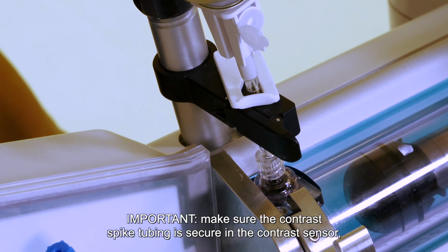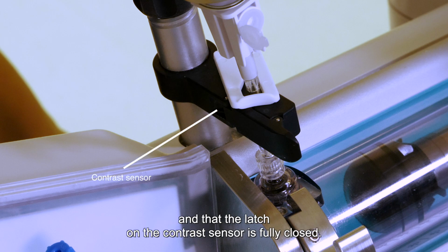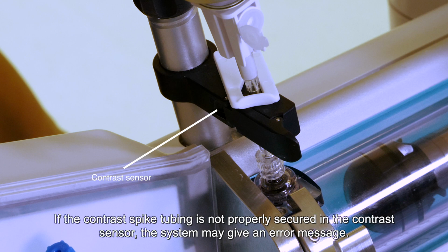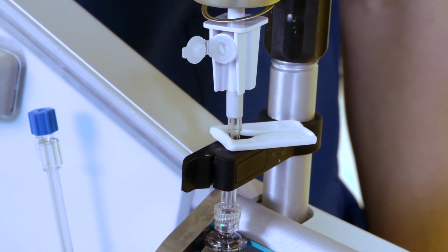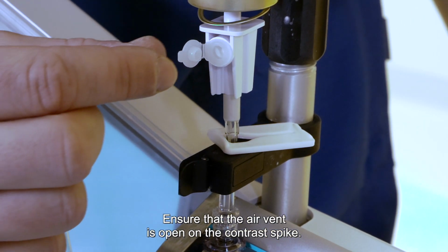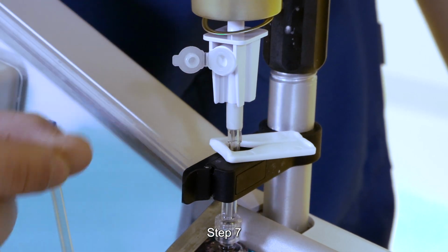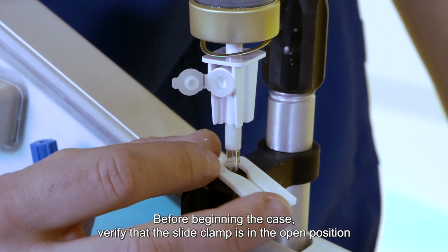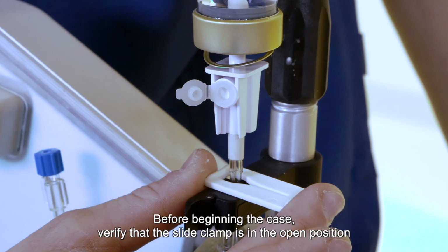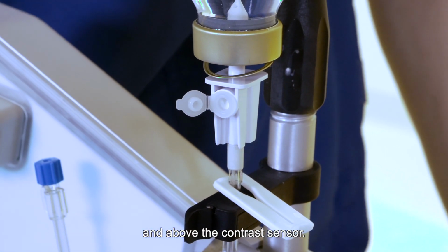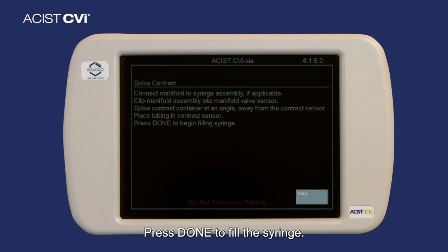Important: make sure the contrast spike tubing is secure in the contrast sensor and that the latch on the contrast sensor is fully closed. If the contrast spike tubing is not properly secured in the contrast sensor, the system may give an error message. Step 6. Ensure that the air vent is open on the contrast spike. Step 7. Before beginning the case, verify that the slide clamp is in the open position and above the contrast sensor. Press Done to fill the syringe.